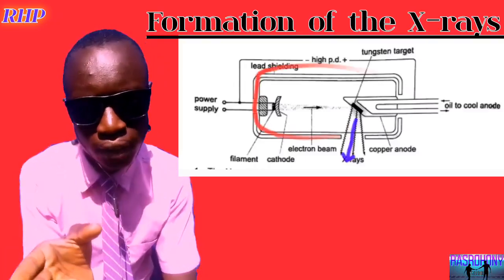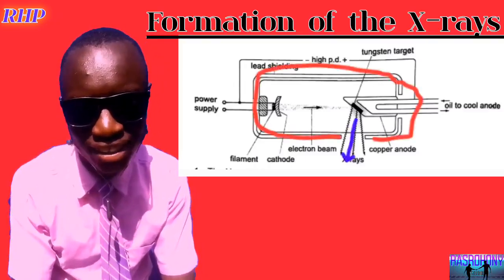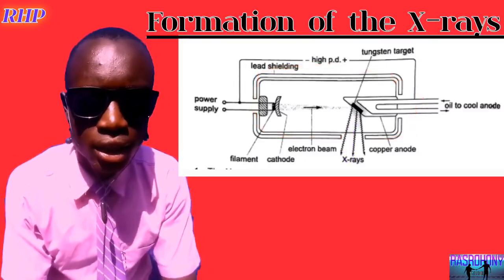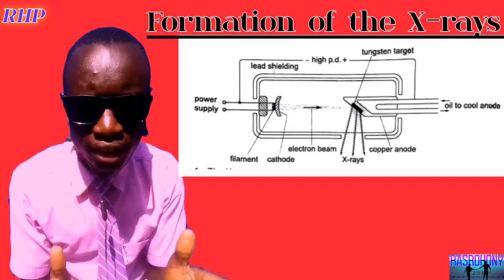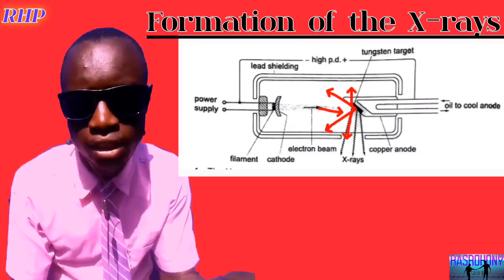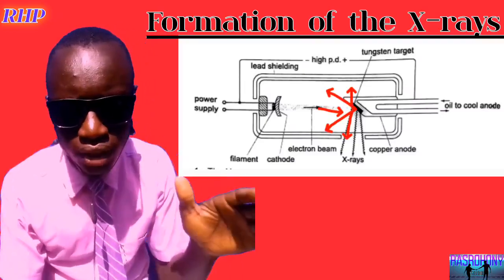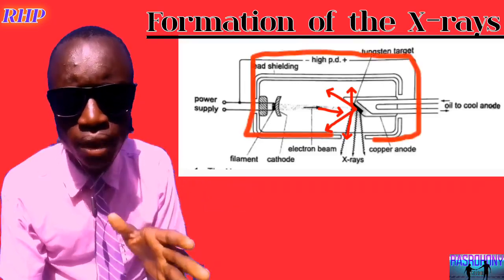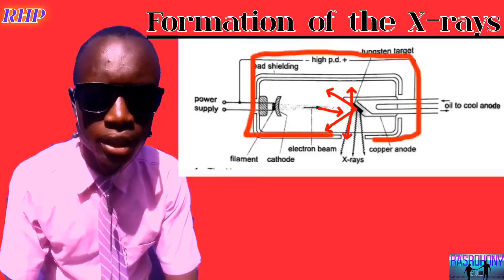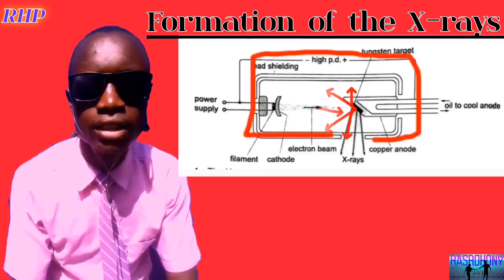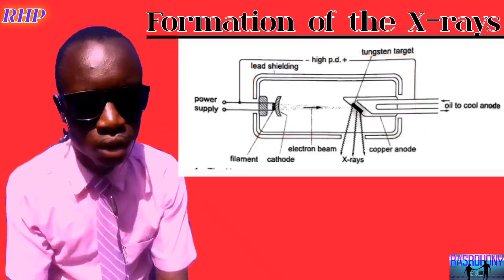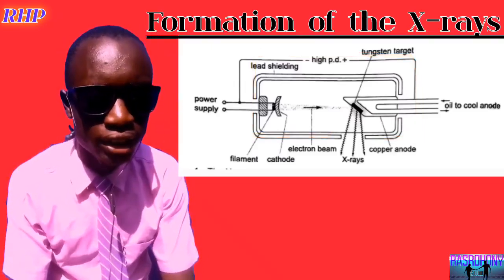That window is in the lead shield. What is the purpose of the lead shield? The lead shield is there to stop the rays that will be reflected to different angles, preventing them from escaping in other directions. The X-ray cannot penetrate the lead. That's why lead is used. And the X-ray will be redirected through the window. Intensity of the X-ray.